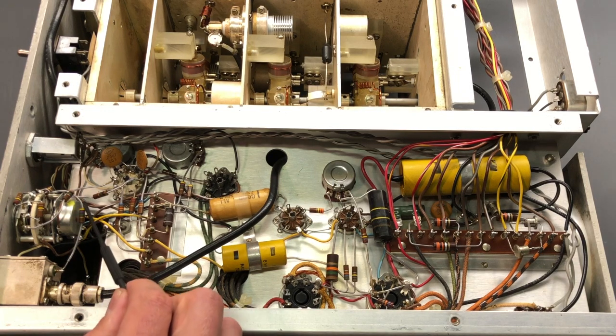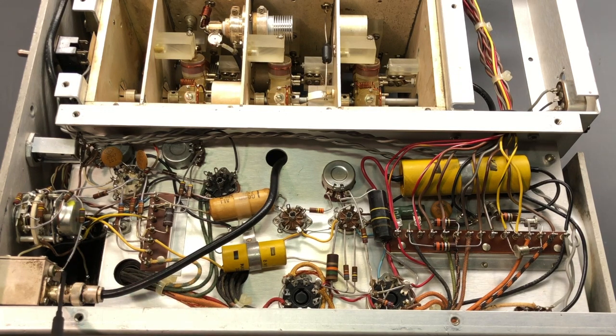Okay, right here you can see there's a resistor that comes over to a solder connection on a feed-through capacitor, and this solder connection was broken. So I've already fixed that, just freshened that up with a little bit of new solder. But that connection was broken. It was just touching. There was a little bit of a J-hook on the end of the resistor lead, and it was just resting against that terminal.